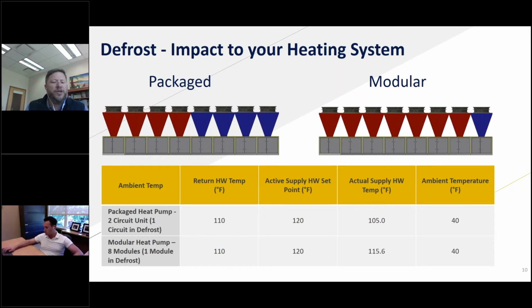Okay, so when we look at that, with return water temperature at 110 degrees, my active set point is 120. The very real possibility while we're in defrost for that packaged unit is that you would be delivering, as I show here, 105 or even potentially slightly lower. It could be potentially slightly higher, but you're going to be in that range depending on how a manufacturer accomplishes defrost. So you're actually going to be providing lower hot water temperature out of the unit than we actually had coming into the unit.